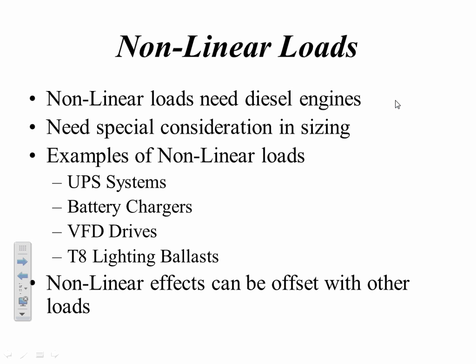They do need special consideration in sizing because of the heating of the neutral. So that's mainly a little bit of oversizing that software programs now take care of. Examples of nonlinear loads: UPS systems, battery chargers, VFD drives, T8 lighting ballasts, and I'm sure you can come up with a few others. Nonlinear effects can be offset with other loads. The nonlinear effects that I saw from a generator perspective were mainly notching on the AC wave. And we could reduce those notching effects by adding more linear load or incandescent lighting type things.